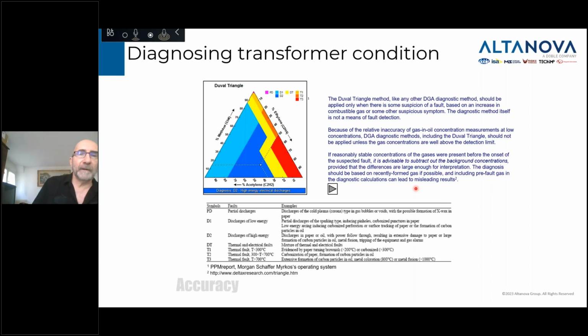The next step, if you go from condition 1 to condition 2, is that you take that DGA data and put it into diagnostic DGA tools. The one that mostly everyone uses around the world is the Dr. Duval triangle. You use three gases: methane, ethylene, and acetylene. By looking at the percentage of each of those gases in the overall total of those three, it gives you a point in one of the areas of the Duval triangle. On this one, you're in D2, what we call high energy discharge.